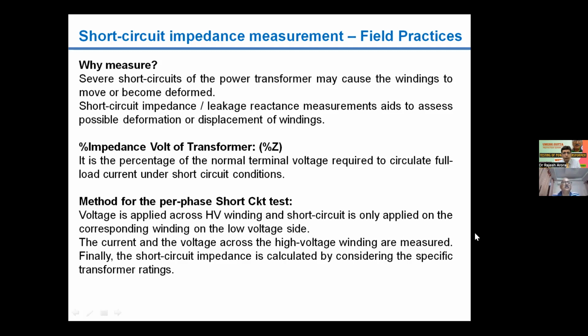The next thing is the percentage impedance voltage of the transformer. It is also an indication of the leakage reactance. It is expressed as a percentage of the normal terminal voltage required to circulate full load current under short circuit conditions. That means if we short circuit the transformer, how much voltage will be required at the terminal of the transformer to inject the full load current is the percentage impedance voltage of the transformer. And how is it done? It is done by applying voltage at the HV winding while the LV winding is kept short circuited. The current and the voltage across the high voltage winding are measured.